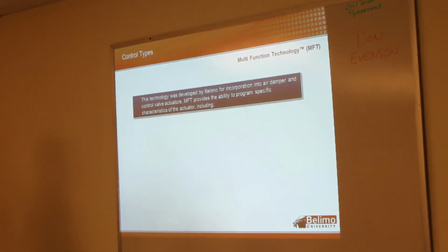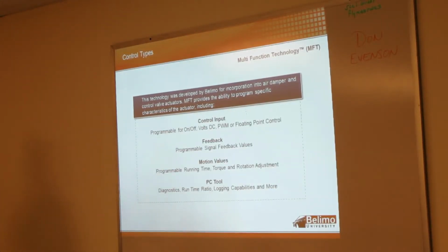So, MFT, like I said, was developed by Belimo for both our air and our valve actuators. It gives you the ability to program specific characteristics of the actuator that include these here. So your control input. Do you want it to be on off? Do you want it to be modulating? We don't use the MFT very often for on off applications because obviously a programmable actuator is going to be quite a bit more expensive than just a two position actuator. It's used very frequently for modulating applications.